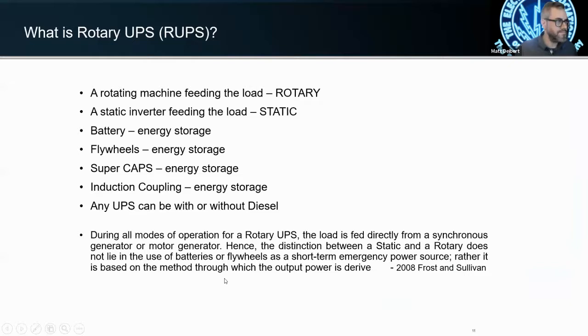Let's talk about what a rotary machine really looks like and what it does. And first off, there's a true difference between rotary and energy storage. In fact, as it was most eloquently stated by Frost and Sullivan, basically in a rotary UPS, the load is fed directly from a synchronous generator or a motor generator, more commonly known as an MG. The distinction between the static UPS and the rotary UPS doesn't lie in the energy storage, okay? It's the function of how the machine gives you protected power downstream.